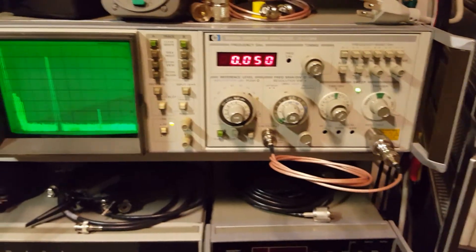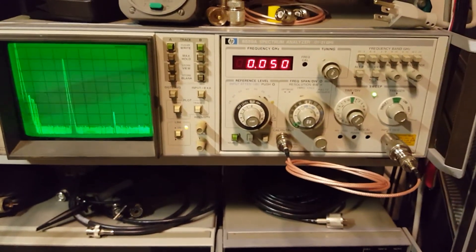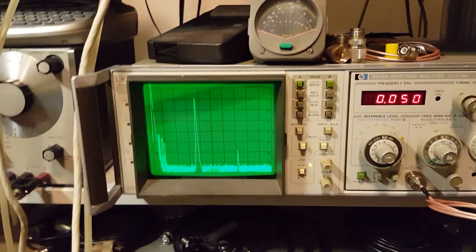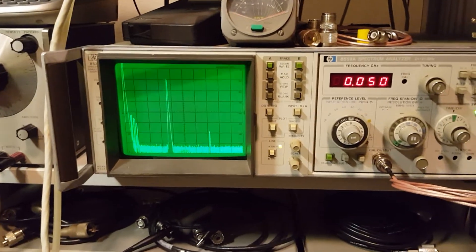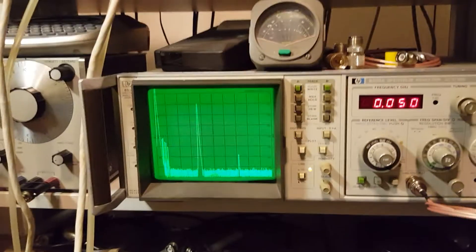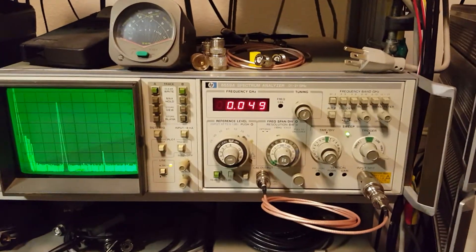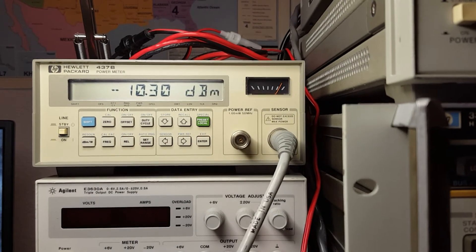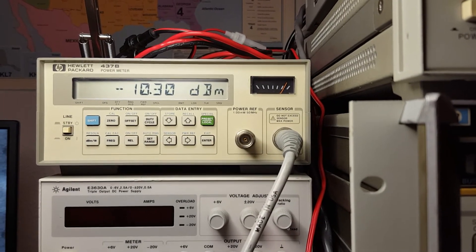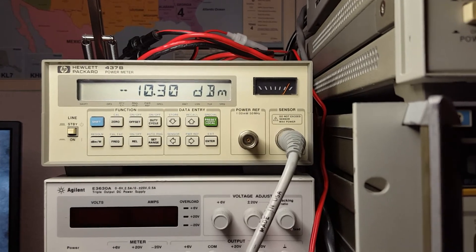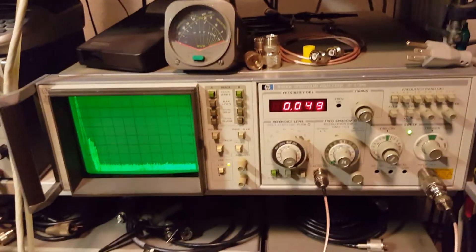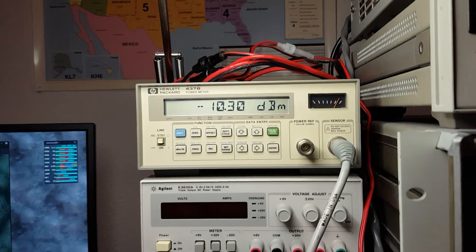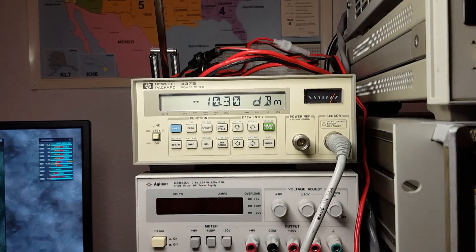Next thing we'll do is try checking the calibrator output of this spectrum analyzer. It's supposed to be minus 10 dBm, that's what it's showing here on the display on the CRT. Here we are: 10.3 dBm, minus 10.3 dBm. Not bad. We could tweak it in a little bit using the adjuster, but I think we'll just leave it there for now.